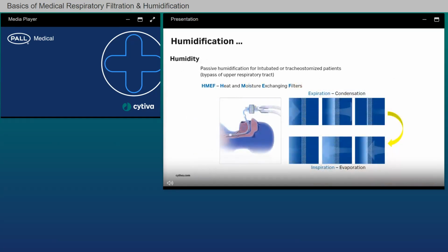And now we get to the exciting functionality of hydrophobic pleated filter membrane and how important they are for an optimal humidification of long-term ventilated patients. We're back to the term HMEF. The filter membrane takes over the role of reflecting heat and moisture and filtering the air from pathogens. When the patient exhales, heat and moisture is held back at the membrane, and when the patient inhales, that heat and moisture goes back into the lungs. And how effective that can be is what we go into next, which is our final subject for today.